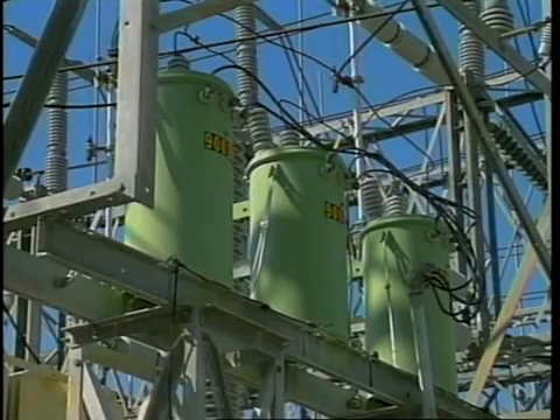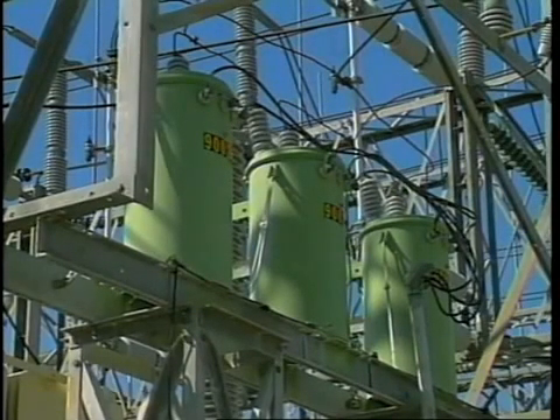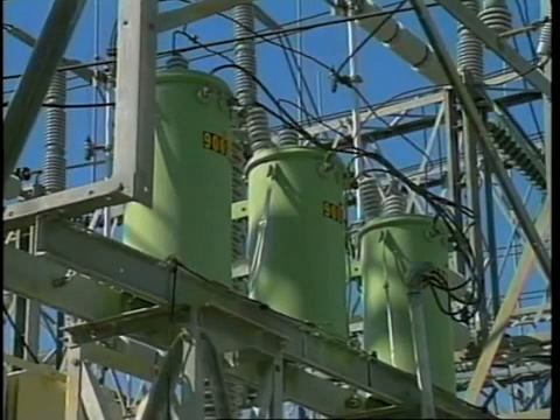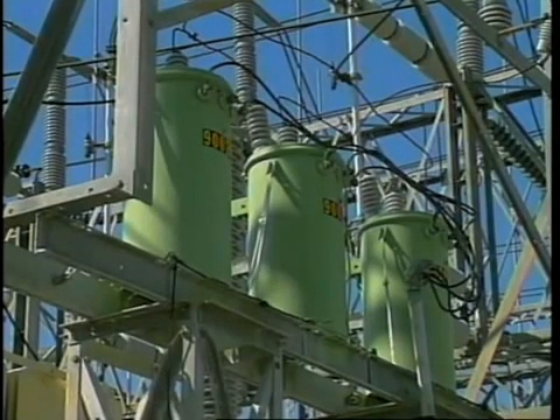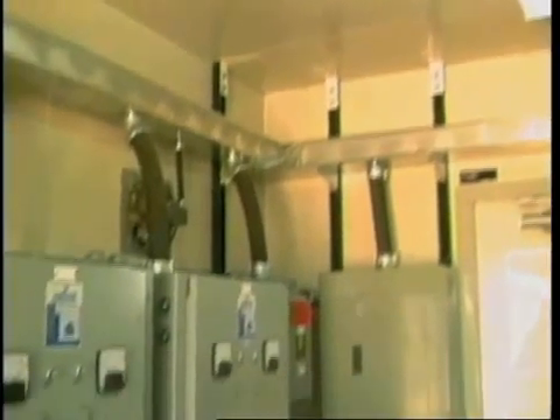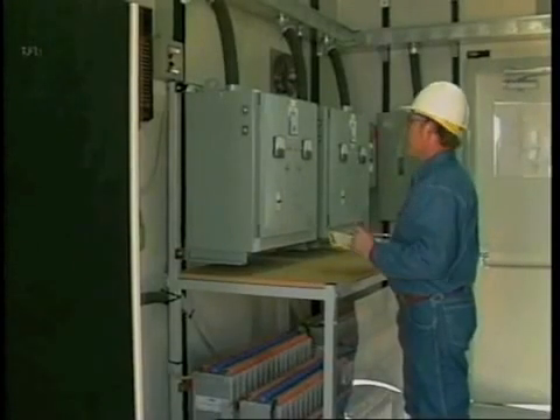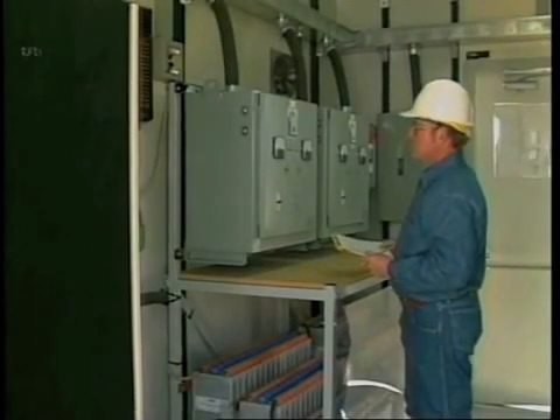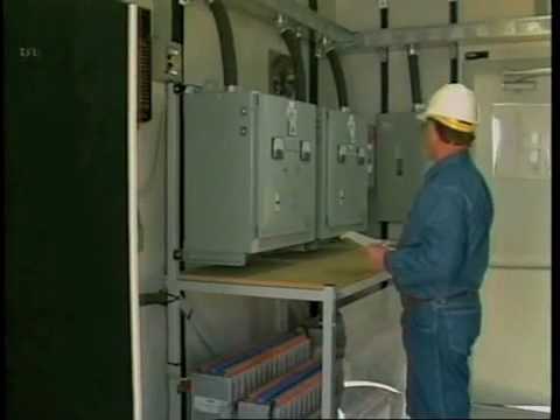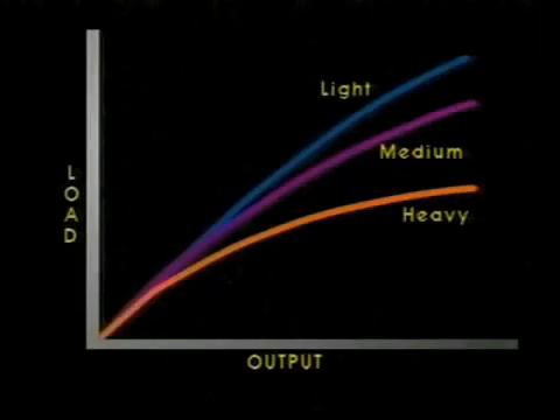Control power transformers are less expensive and physically larger than other types of potential transformers. They are used for lighting, battery charging, heating, control power, and other similar applications. In selecting a potential transformer, keep in mind the total load of the circuit in which it is to be used. Too heavy a load on the secondary side of a potential transformer can greatly reduce its accuracy and lead to total failure of the device.